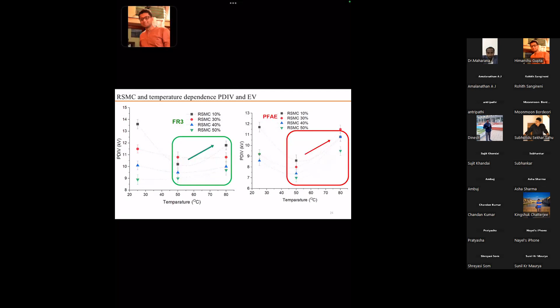PDIV and breakdown voltage are both studied, and there is always a benchmark, say 50 degrees. Till 50 degrees the behavior is different, and beyond 50 degrees the behavior is upward, meaning the PDIV value is increasing. That means the oil is not dependent or influenced by moisture as much, and it is not very much conducting, so it is not allowing the breakdown easily. There is a possibility, so we have studied this kind of phenomena here. There will be some molecular disarrangement, and we need to figure out the possible phenomena involved, so we can conclude why there is a change below and above 50 degrees.